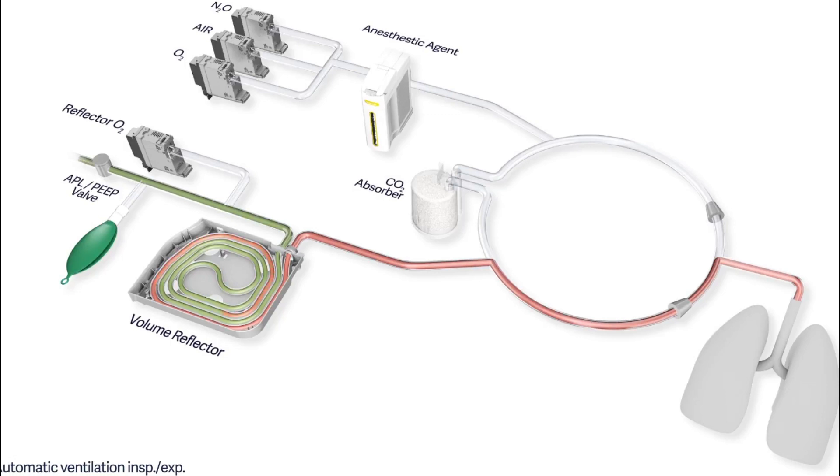The fresh gas flow must meet the exact patient requirements and the soda lime must absorb all expired carbon dioxide. The minimal flow in this system only allows the use of a vaporizer inside circle to be used.